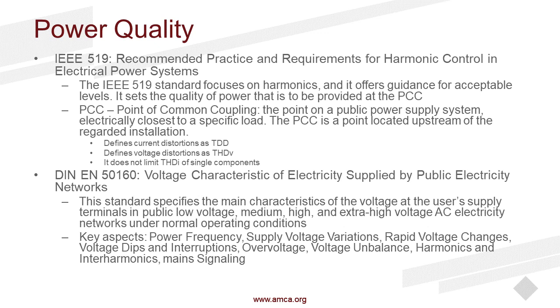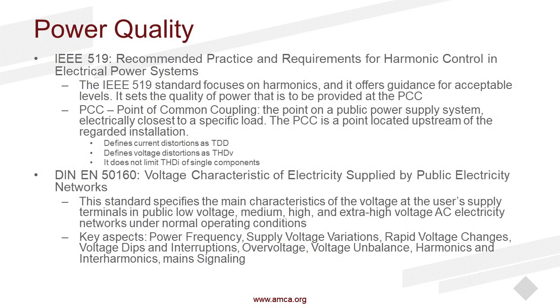So IEEE 519, what it's doing is regulating the harmonics within your system. It's defining current distortions as TDD, or total demand distortion. And it's defining your voltage distortion as THDV, total harmonic distortion voltage. But it's not limiting your total harmonic distortion current of single components. So it's looking at your system as a whole. And then DIN EN 50160 is similar. It's regulating the power quality of low voltage, medium, and high voltage systems. Still looking at your power quality. Just threw that in there. I know most of us are probably looking at IEEE 519.